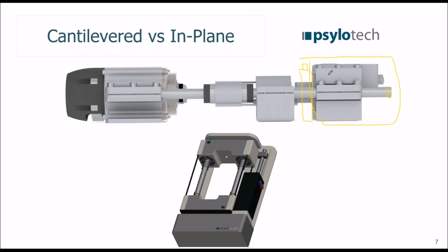That could attach to a crosshead here that also has a motor which applies torsion to everything. So you'd have an axial crosshead here, torsion crosshead here with a torsion load cell. There's a lot of different options, and it's not hard to swap out.